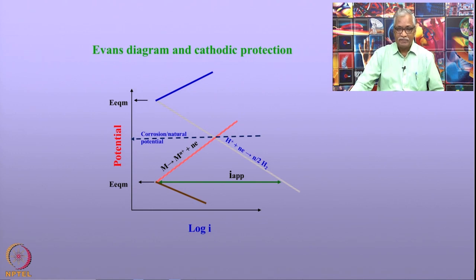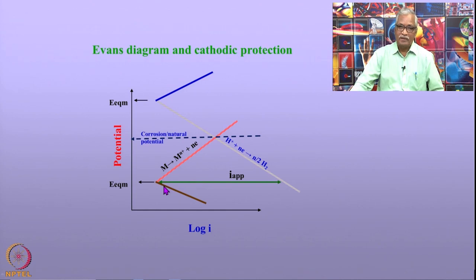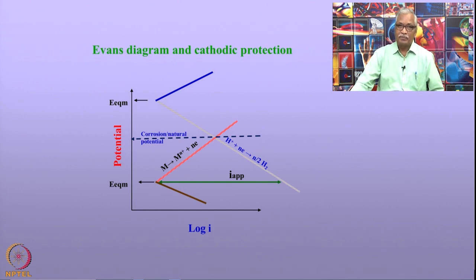In addition to that, there is a significant increase in the cathodic reaction occurring on the metal surface. This is quite damaging if it leads to hydrogen evolution on the metal surface. So on the one hand, you want to minimize the corrosion rate by bringing down the potential as close as possible to the equilibrium potential. On the other hand, you need to supply a large amount of current density, and there is also a likelihood of the metal getting damaged because of hydrogen evolution. If the pipeline is coated, there will be damage to the coating.